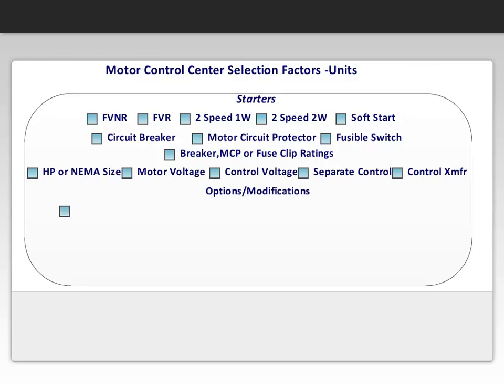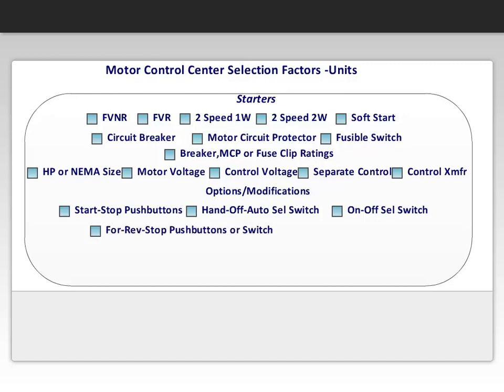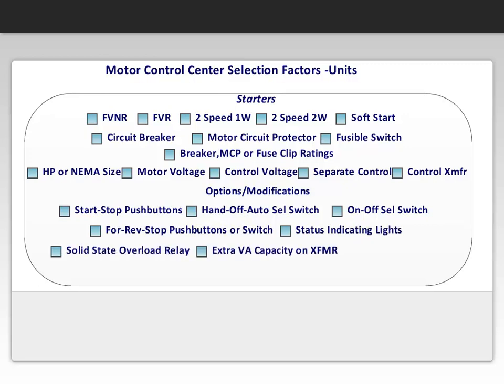Does he want a start-stop push button, hand-off auto selector switch, on-off selector switch? And for a full voltage reversing application, does he want a forward reverse stop push button or switch? And if any status indicating lights are required. Does the customer require a solid-state overload? Is there extra capacity required on a transformer? The number of auxiliary contacts that are required? And if it's a replacement, we need to know the manufacturer and the motor control center model.